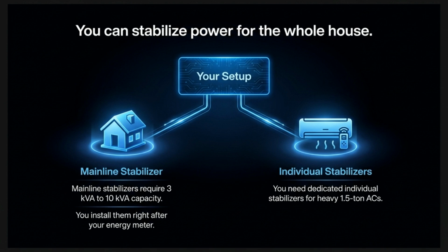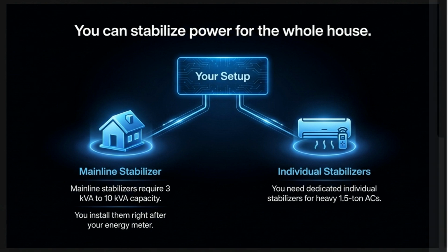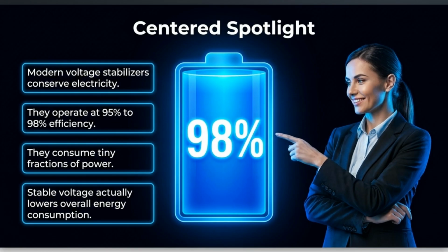You can stabilize power for the whole house using a mainline stabilizer with 3 kVA to 10 kVA capacity installed after your energy meter. Alternatively, use dedicated individual stabilizers for heavy appliances like 1.5-ton ACs. Modern voltage stabilizers are highly efficient, operating at 95% to 98% efficiency. They consume tiny fractions of power, and stable voltage actually helps lower overall energy consumption.